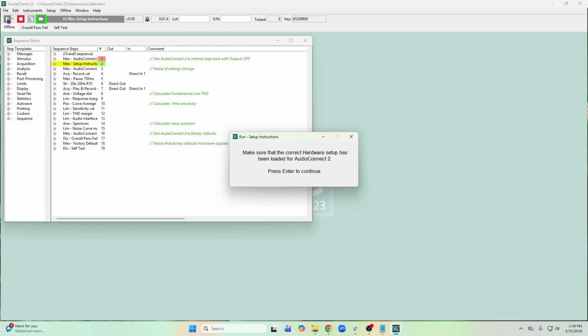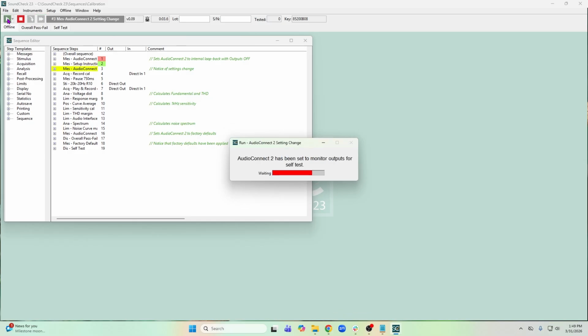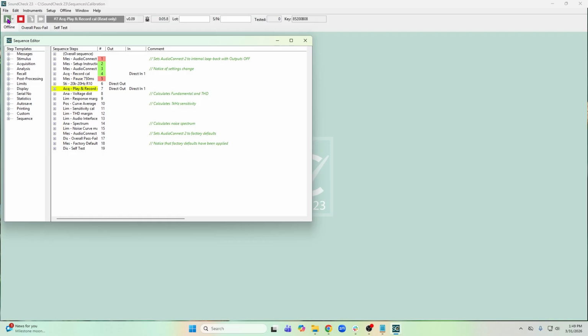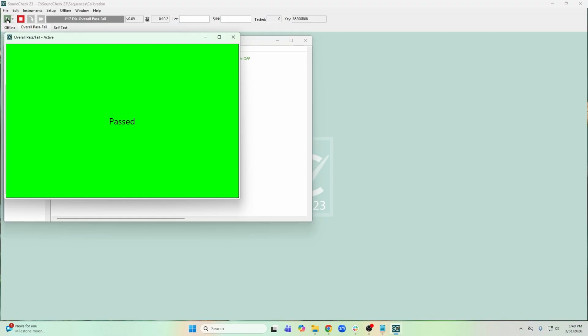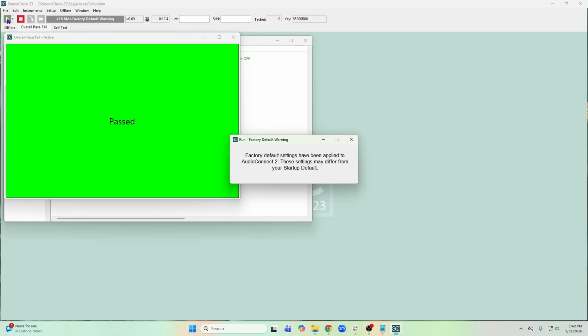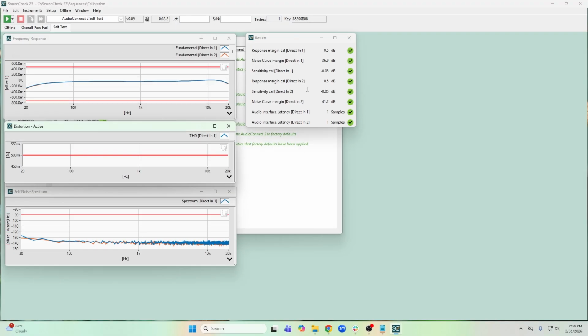This configures the AC2 to internally loop back the outputs to the inputs, and it makes sure that it's able to send and receive signals without relying on external cables or transducers. This can be used as a sanity check to make sure everything in SoundCheck's hardware table is set properly and there's no issue with the device. As we can see, the unit has passed self-test. This is an important step. Don't skip it. Now everything is configured and we're ready to make a measurement. Let's do a quick demo.